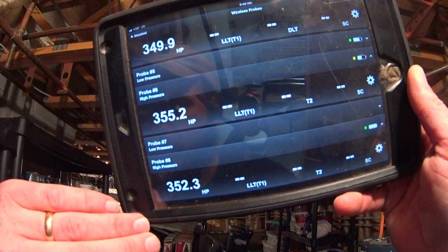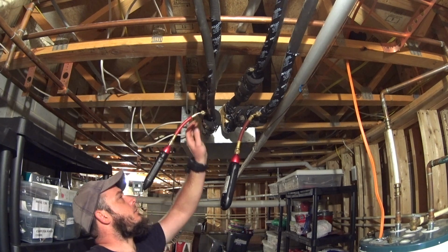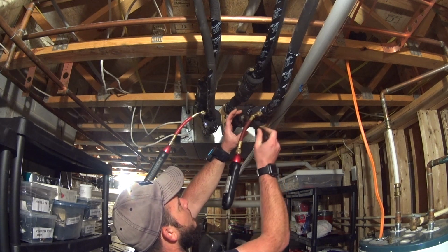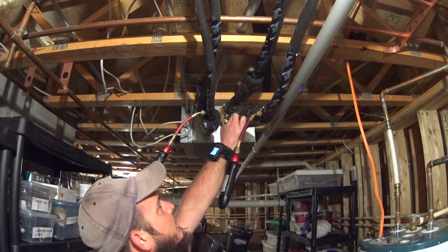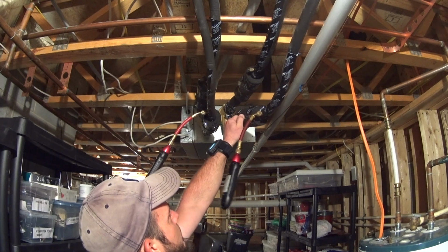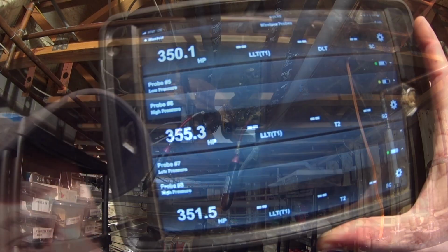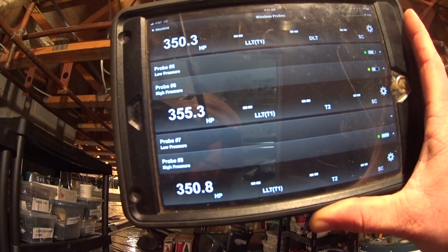We've got about 350 on each zone, so we're going to isolate and see which one falls. This first zone is the one that is in question with the electronic leak indication. The second one is the shop unit directly behind you. So now we're isolated. We're starting off at 355 for the shop unit and 350 for the other one, and the overall pressure test is 350.